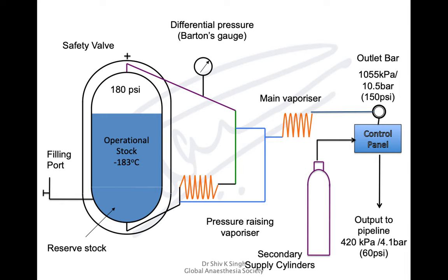The VIE has different ports: a filling port for liquid oxygen, a top port for the gaseous form, and a safety valve at the top to vent when pressure gets too high. There is also a lower port through which liquid oxygen can be withdrawn during high demand, and it passes through a vaporizer. The amount is measured by differential pressure — measuring pressure at top and bottom. Older types used three legs with one on a hinged scale, but modern ones use differential pressure monitoring.